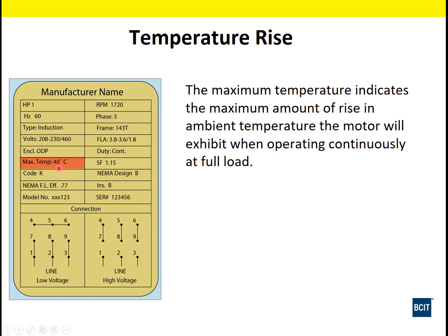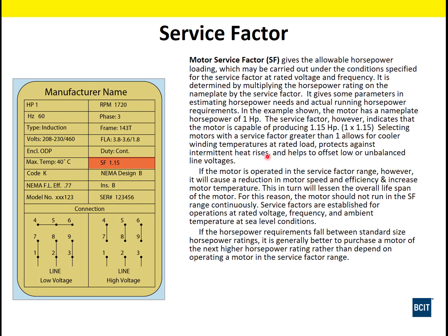Max temperature, 40 degrees C. This is the maximum ambient temperature that the motor can operate at before we have to start derating it continuously. Service factor. I'm not going to read this to you. In a nutshell, this 1 horsepower motor is actually sized to be 1.15 horsepower. So it can run effectively up to that amount. What that does is, we're running it slightly unloaded, and it'll run cooler. We're not hitting its maximum design limits. It also gives us a little bit of a margin in sizing our overload. So when we have this type of service factor, we can size our overloads at a slightly higher percentage than the FLA if we need to.